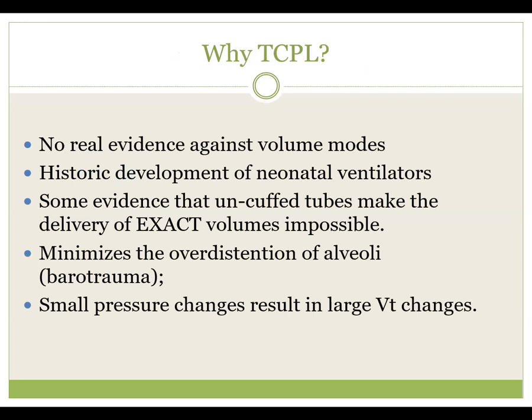Small pressure changes result in large tidal volume changes, so we go up by 1 or 2 at a time. We go down by 1 or 2 at a time. If you have an infant-specific ventilator, it's easier and cheaper to manufacture pressure controllers, or pressure generators.